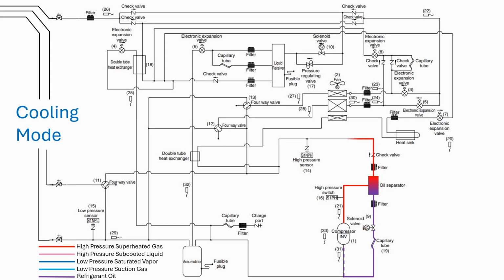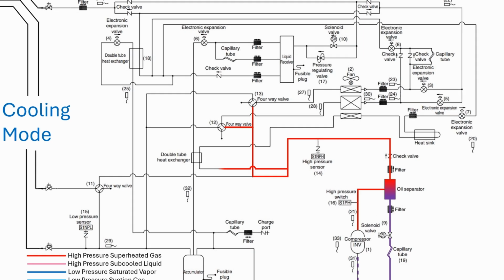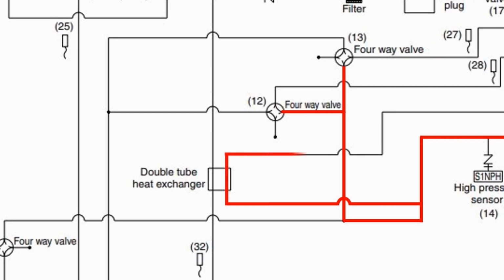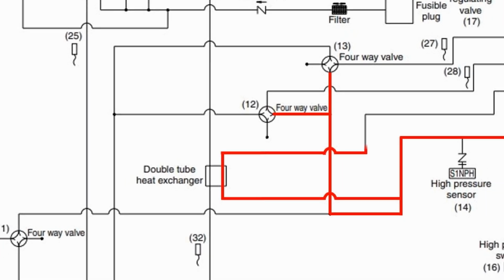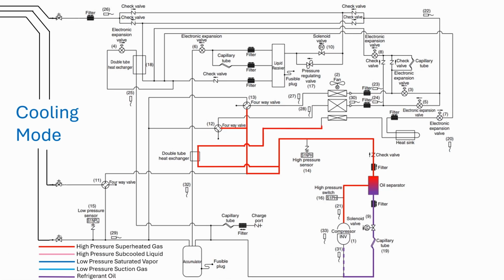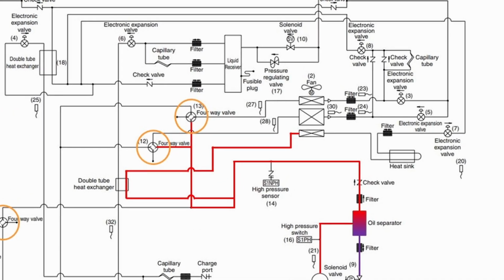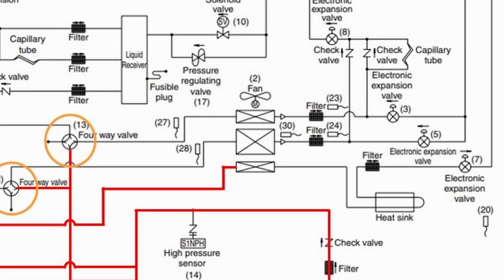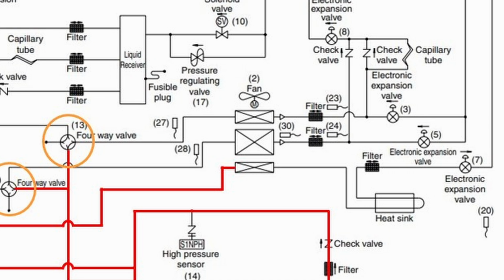As the refrigerant leaves the oil separator, it too passes through a filter or bullet strainer on its way to its first stop, which is a tube-in-tube heat exchanger or subcooling coil. From the tube-in-tube heat exchanger, the refrigerant travels to its first section of outdoor coil. Notice that this particular diagram has 3 four-way valves. Also notice that the outdoor unit heat exchanger is divided into 3 separate compartments.